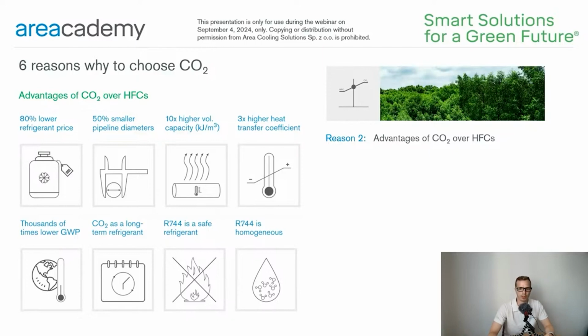Thanks to this, there is no temperature glide and pressure drop. The system charging is also simplified. CO2 can be charged into the installation in gaseous form without the stratification problems that occur with zeotropic HFC refrigerants, 400 family, due to the different boiling points of the components.